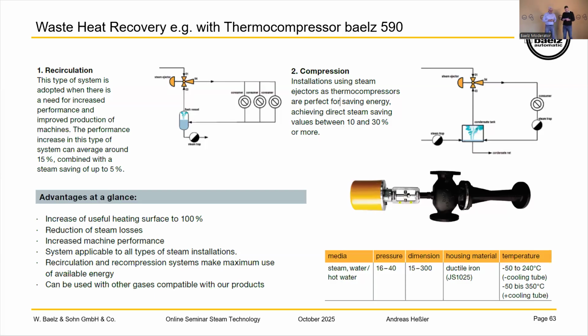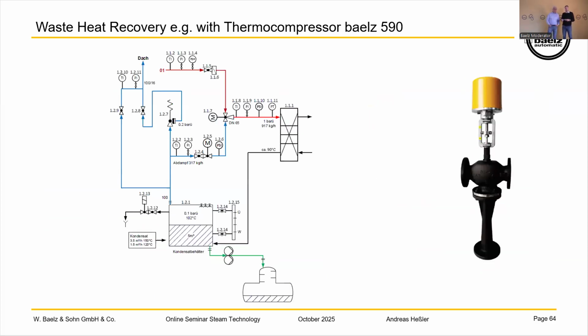Another question having to do with the BAELZ 590. Does the steam being raised in pressure, so the low pressure steam, by the thermocompressor need to be clean, or can we just use process steam? Right. It has to be clean. But it's normally clean, because when you see this picture, you normally come with the flash steam, or with the suction steam. You come in normally from the flash vessel or from the condenser. So that's normally clean. If you come from process, it would be better to use a strainer or something like that.